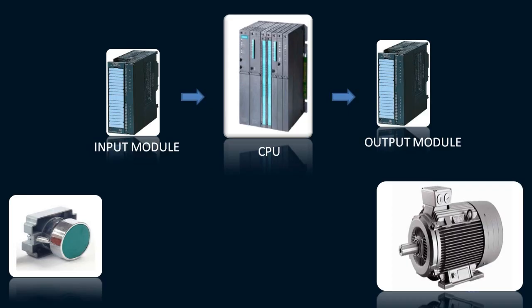The output card is interfaced with the final control element — like a motor — and it will give the signal to the motor that it is time to start. The push button is sending a command to the input card of the PLC. The input card is just an interface between the PLC CPU and the field device — in this case, the push button. You get the signal from the push button through the input module, which is the interface between your CPU and the field element.